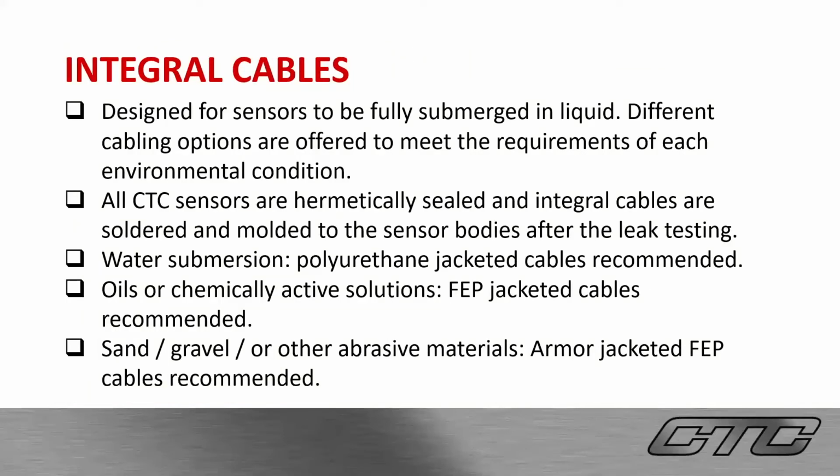Now we'll start talking about our integral cabling options. These are designed for sensors to be fully submerged in liquid. Different cabling options are offered to meet the requirements of each environmental condition. All CTC sensors are hermetically sealed, and integral cables are soldered and molded to the sensor bodies after they are leak tested. For water submersion, polyurethane jacketed cables are recommended. For oils or chemically active solutions, FEP jacketed cables are recommended. And for sand, gravel, or other abrasive materials, armored jacketed FEP cables are recommended.